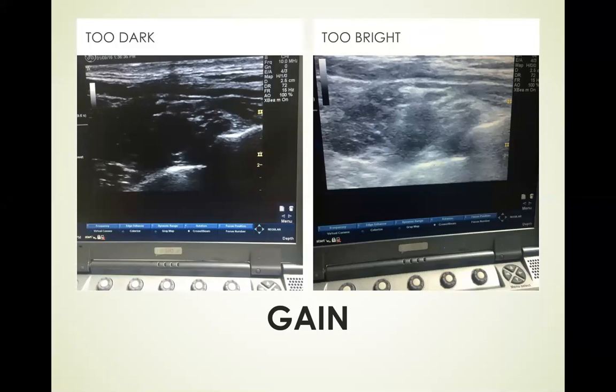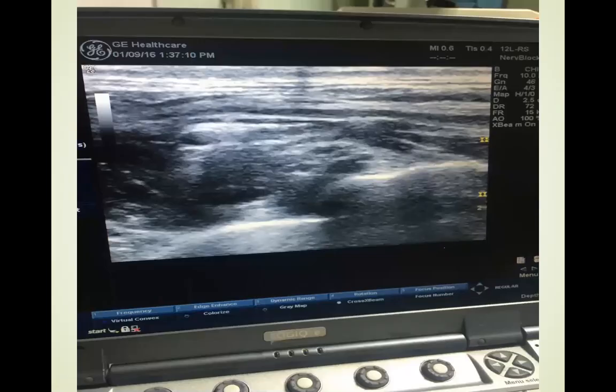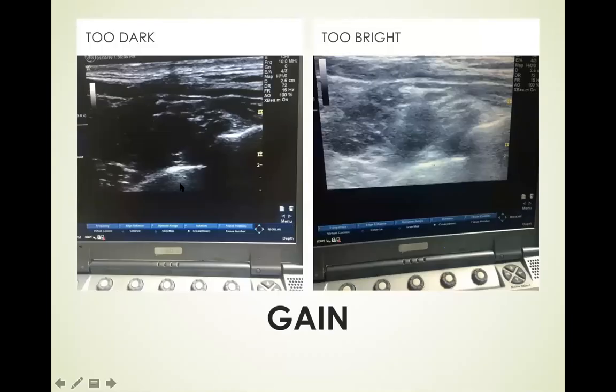Regarding the gain: this is too bright an image, and this is too dark an image. Whenever you increase the gain, there will be more brightening of the image like this. So if you face such an image, you can decrease the gain. If you face a dark image, you can increase the gain to get a more suitable and nice picture like this, which is homogeneous, with a good relation between white and black in the image - not like this, which is too dark, or like this, which is too white.